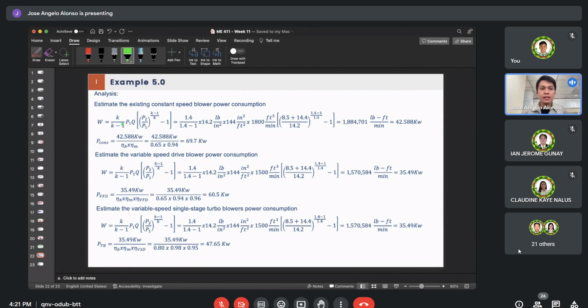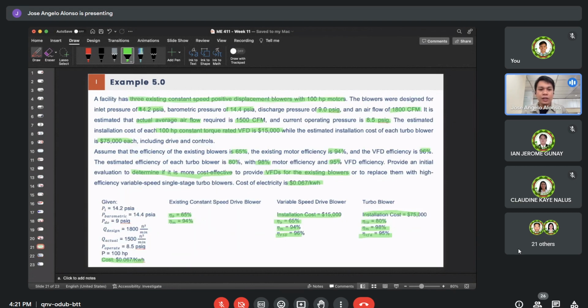Since K wasn't given in the problem, we will use 1.4 as stated earlier. The inlet pressure is 14.2 psi, given here in the design. So the design inlet pressure is 14.2 psi absolute. We need to convert this.